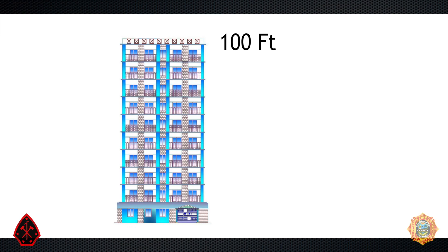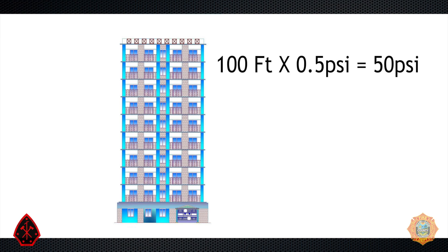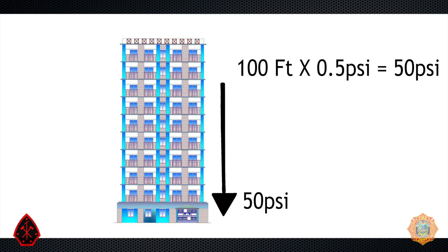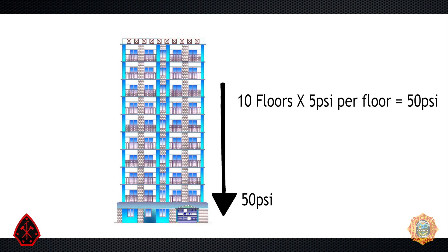Consider a 10-story building. If the building was exactly 100 feet high, that would be 100 feet of elevation times 0.5 psi, which equals 50 psi of head pressure at the base of the riser. Another way of calculating elevation loss is to take the number of floors — in this case 10 — times 5 psi per floor. The answer is the same: 50 psi of head pressure at the base of the riser.